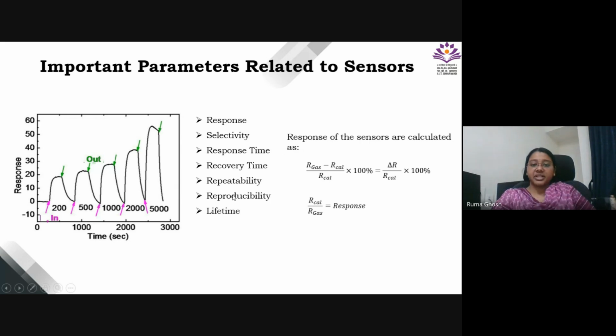Next is repeatability. Let's say what I have done here is we have exposed the sensor to multiple different concentrations of the same gas. Now, what if I had exposed this sensor to the same concentration of the gas multiple times? Let's say 5 times, 10 times, 100 times. My desired output is, let's say if the response is 40% here, even if it goes to 100 times, it should be 40% only.